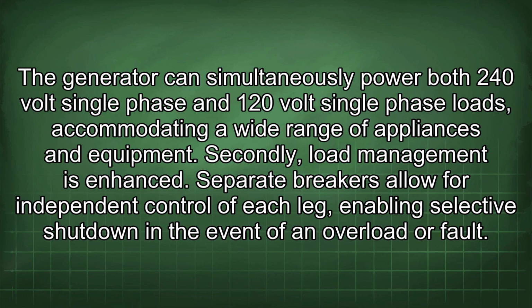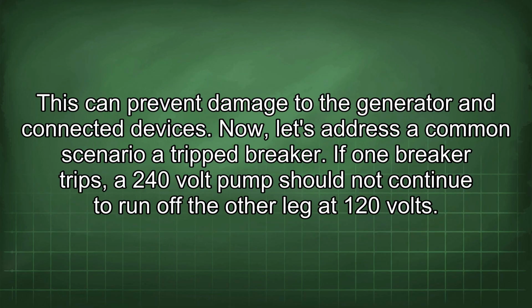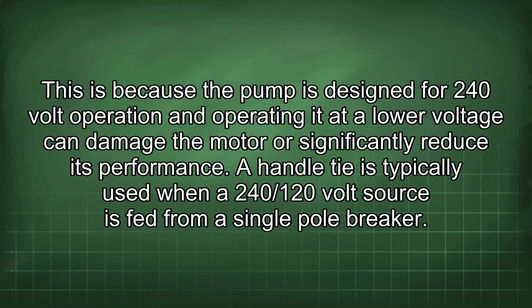Separate breakers allow for independent control of each leg, enabling selective shutdown in the event of an overload or fault. This can prevent damage to the generator and connected devices. Now let's address a common scenario: a tripped breaker. If one breaker trips, a 240-volt pump should not continue to run off the other leg at 120 volts. This is because the pump is designed for 240-volt operation, and operating it at a low voltage can damage the motor or significantly reduce its performance.